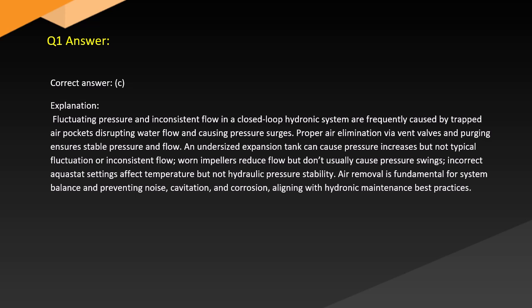Answer. Correct answer: C. Explanation. Fluctuating pressure and inconsistent flow in a closed-loop hydronic system are frequently caused by trapped air pockets disrupting water flow and causing pressure surges. Proper air elimination via vent valves and purging ensures stable pressure and flow.